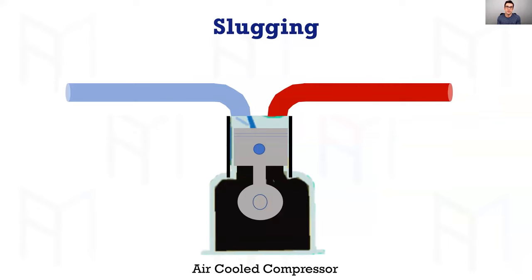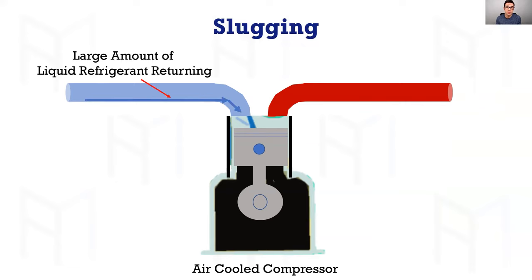Next, air-cooled compressors. You can tell an air-cooled compressor — for example a Copeland K-body — by looking at the head where you'll have your discharge and suction right on the head. When an air-cooled compressor takes a slug, it happens differently than a scroll. You have a large amount of liquid refrigerant returning, and this happens through flood back — you lose control of the evaporator. The fans aren't running, it ices up, you have a dirty coil — all those things can lead to a large amount of liquid refrigerant coming back because you cannot boil off that liquid refrigerant.